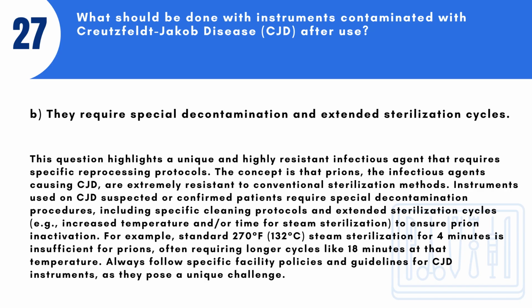For example, standard 270 degrees Fahrenheit, 132 degrees Celsius, steam sterilization for 4 minutes is insufficient for prions, often requiring longer cycles like 18 minutes at that temperature. Always follow specific facility policies and guidelines for CJD instruments, as they pose a unique challenge.